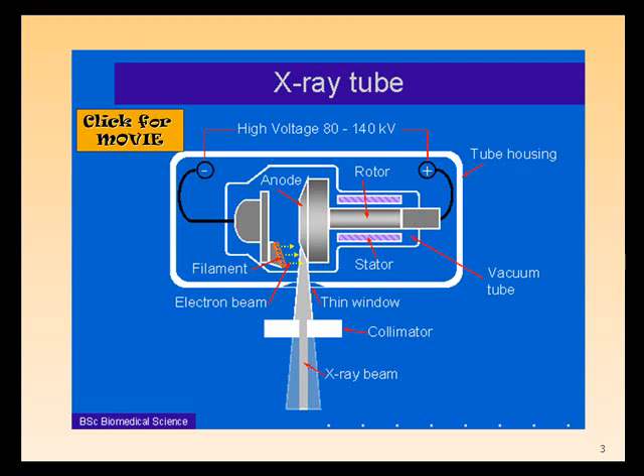The high voltage is 80 to 140 kilovolts between the two. Kilo is 1,000 volts, so we usually go up to 140 kilovolts. The higher the energy, the more penetrating the X-rays are.